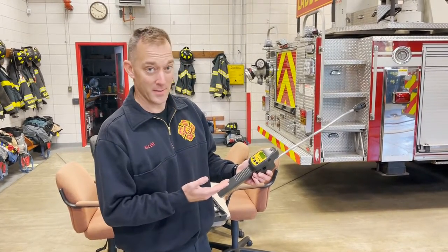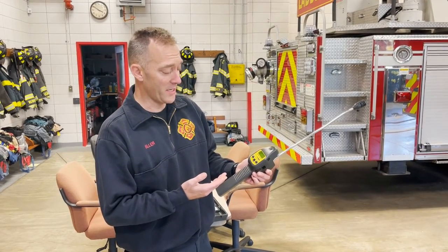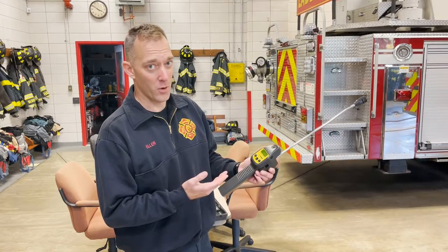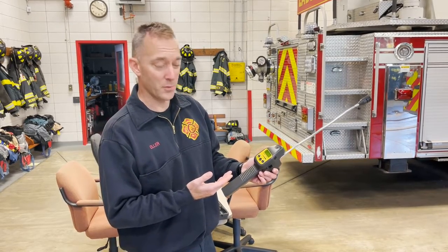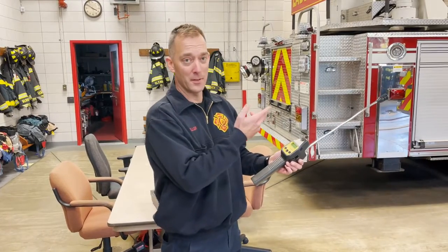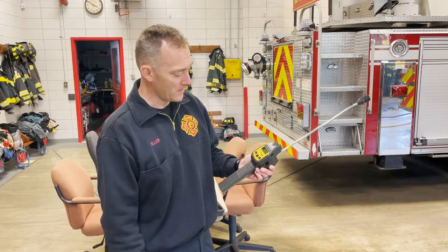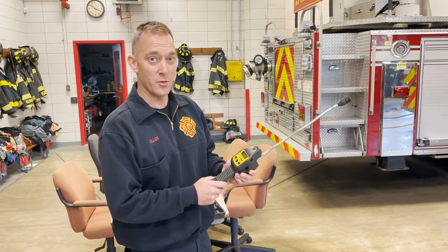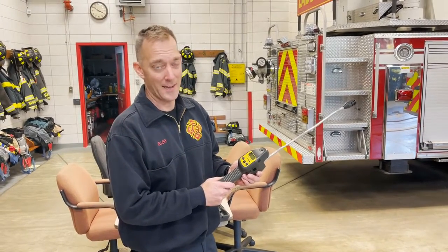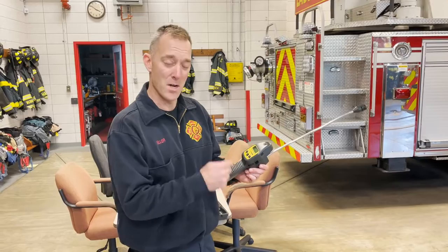This has a semiconductor or metal oxide type sensor on it, which is far more sensitive to combustible gases than the electro-catalytic bead sensor that's on the MSA 5 gas. So if you are trying to track down the source of a natural gas leak, this is your go-to instrument. You can also use the 5 gas, but this is going to be much more sensitive.